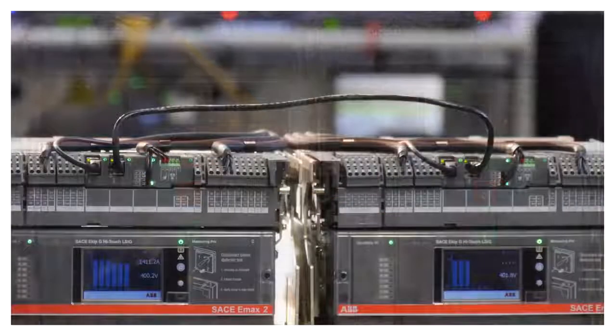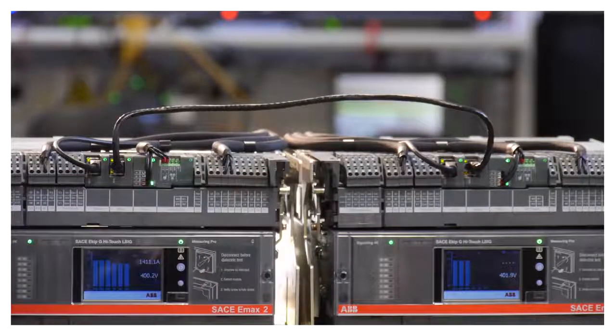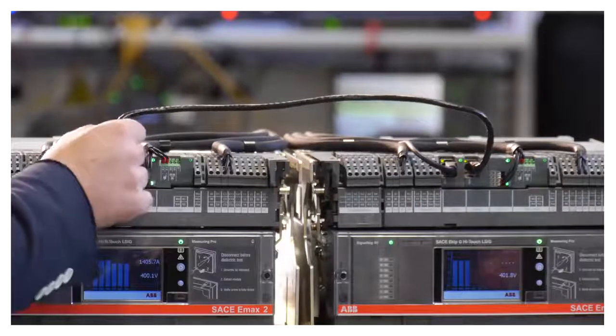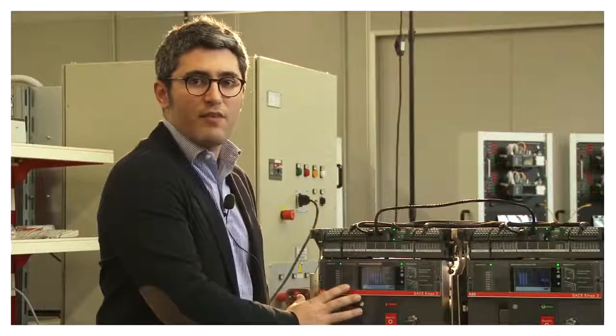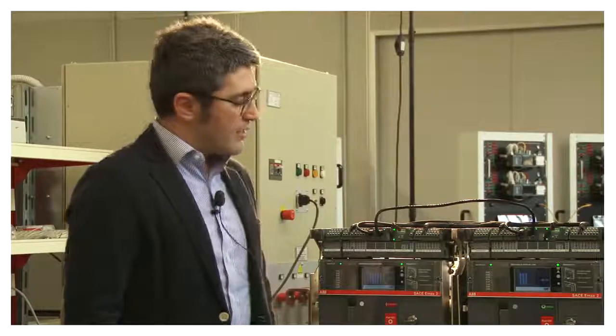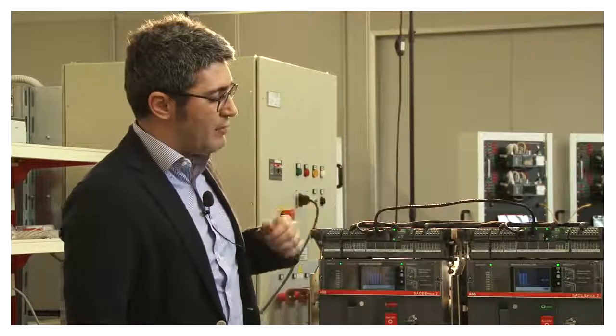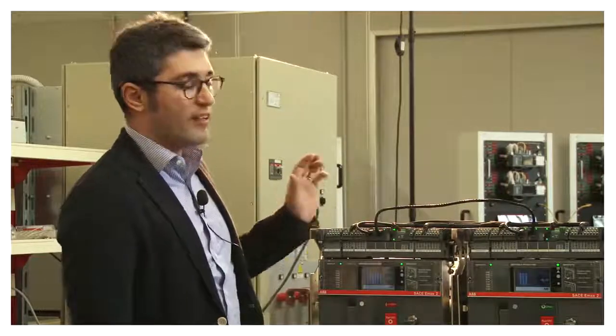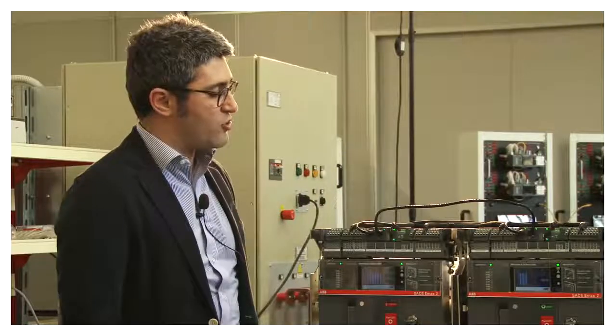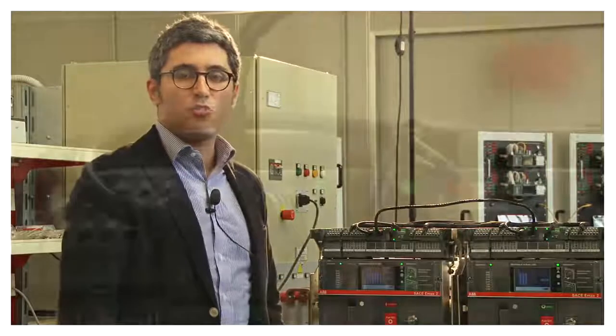Thanks to the Ekip Link modules it's possible to create a direct communication between trip units using a high speed communication bus called Link and able to exchange all information from one device to another one. In this way it's possible to make automatic transfer switch or more complex logics. As you can see here, it's enough to have only one cable to make all this type of application without using external cabling, external sensor or additional external unit. That means a very optimized solution for your switchboard.